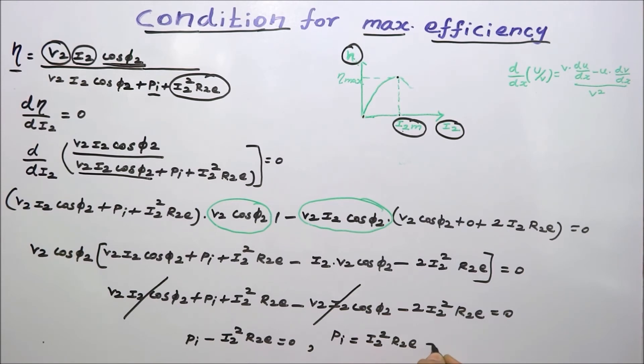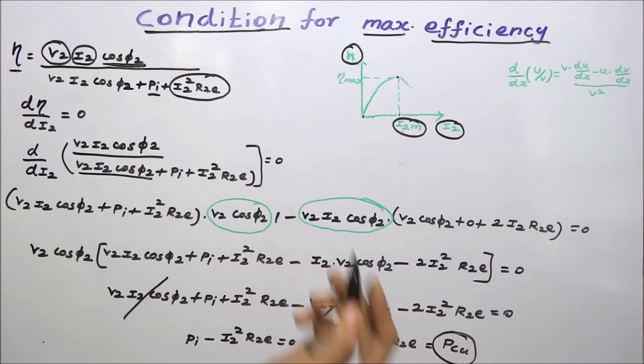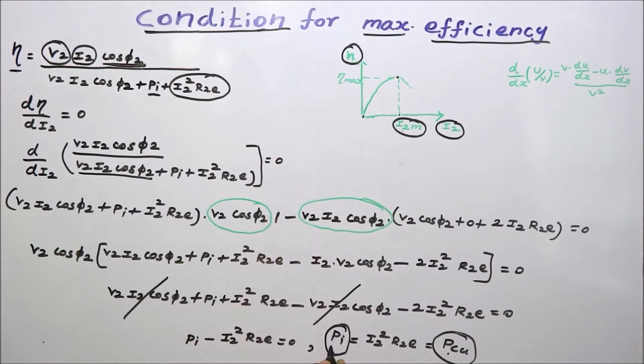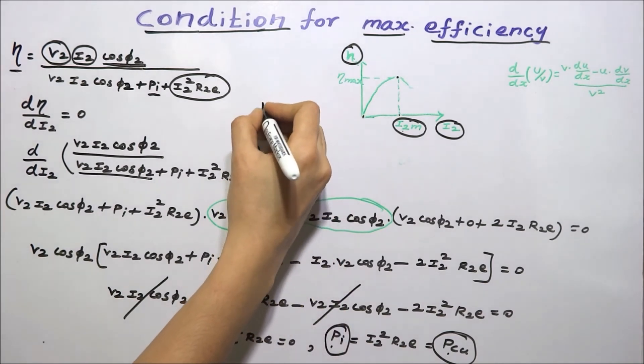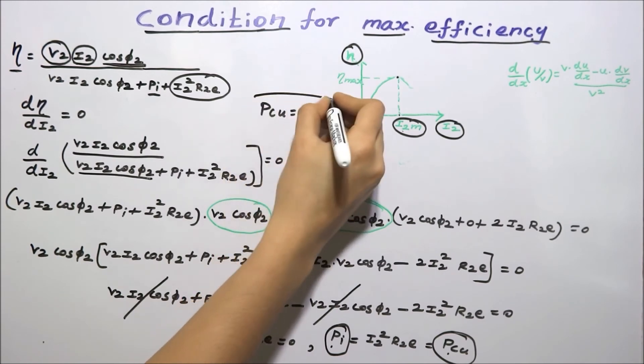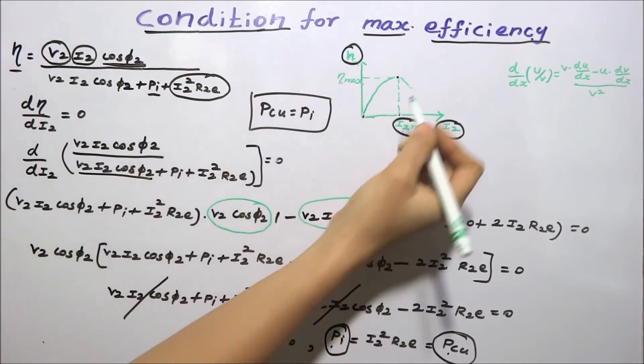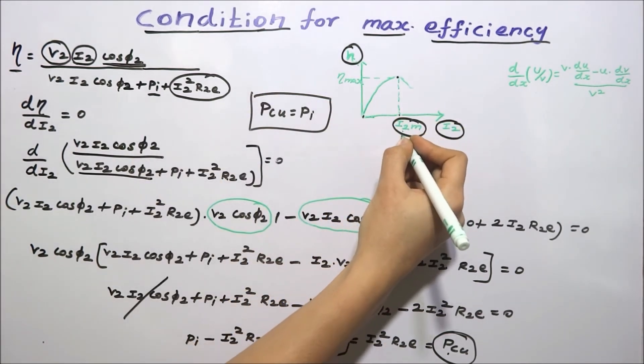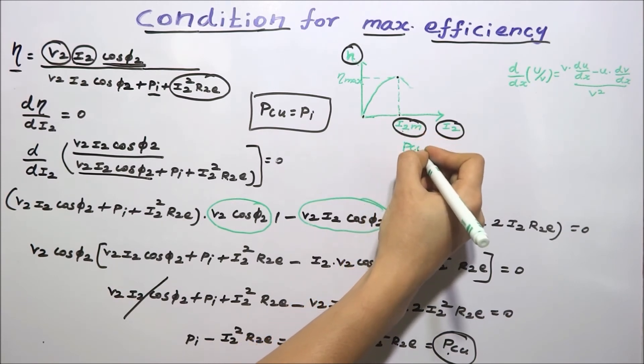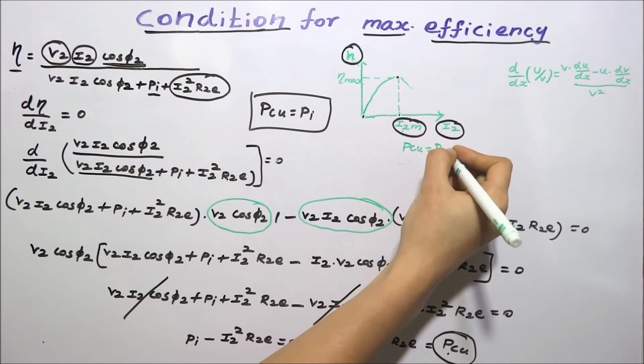Since I2²·R2E is the copper loss, the condition for maximum efficiency is that the iron loss must equal the copper loss: P_copper = P_iron. The load current I2M attains the value at which maximum efficiency occurs precisely when the copper loss equals the iron loss.